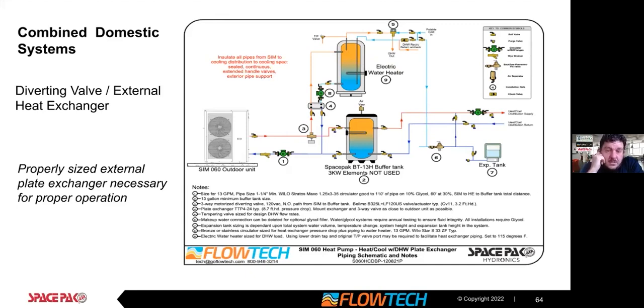And the other one is it's critical to use an externally sized flat plate heat exchanger. I get asked a lot from my technicians, hey, I've got an indirect here. There used to be a boiler. I just want to run it into the indirect, and it's not going to work. It's a bad situation. Won't deliver the heat to the unit, and then the SpacePak starts to think it's satisfying the load, and it will ramp down, and you'll never satisfy that domestic load. So it's real critical in this application to use the external flat plate heat exchanger.